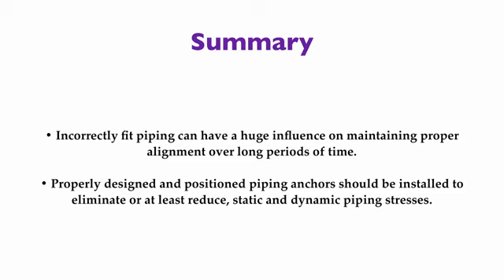Piping can have a huge influence on the alignment and positional stability of our rotating machinery. Proper piping fit-up is critically important, and even though pipe fitters may not be responsible for aligning machinery, they need to know how their pipes can wreak havoc on our desire to keep machinery aligned for long periods of time. Piping anchors may need to be added to ensure no, or at least very little piping strain impinges on our equipment.